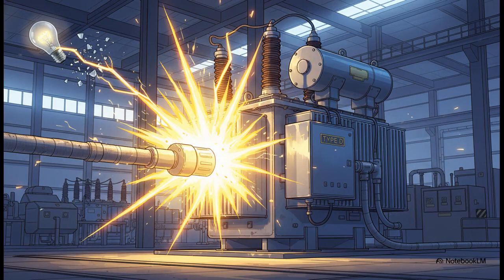And finally, there's Type D. This one's the big guy, the industrial heavyweight. It's designed to handle massive inrush currents from things like giant industrial motors or transformers. Because it's not very sensitive, it is almost never the right choice for a home. In fact, putting a Type D breaker on a regular lighting circuit would be incredibly dangerous.